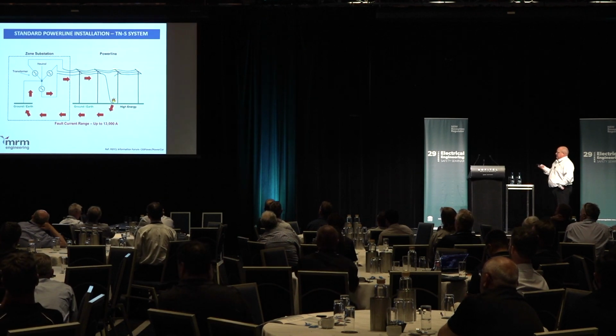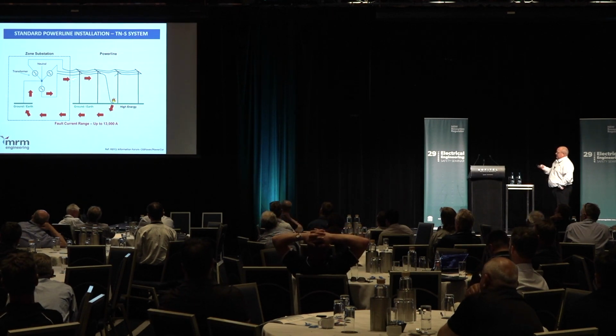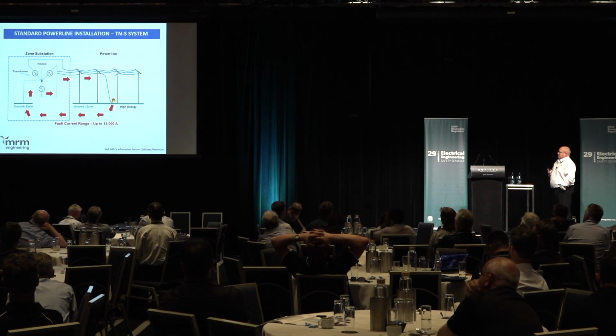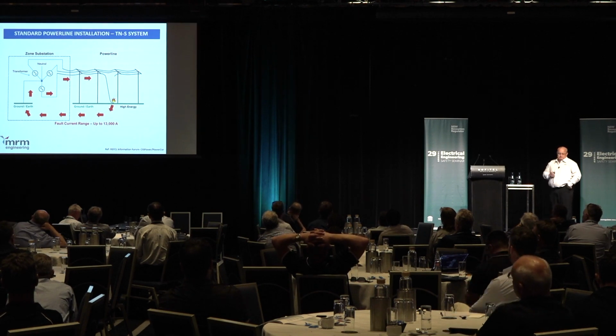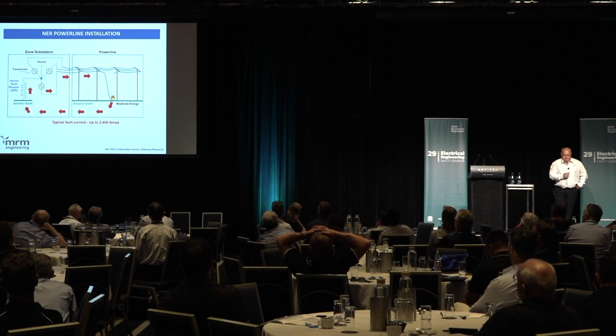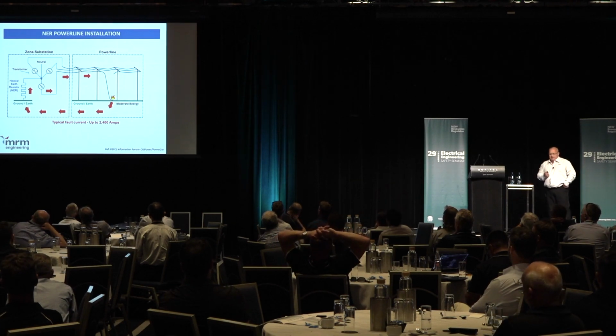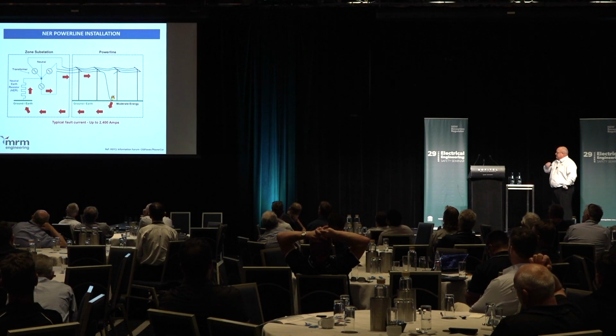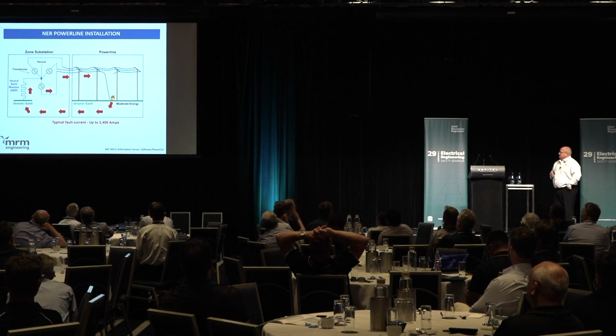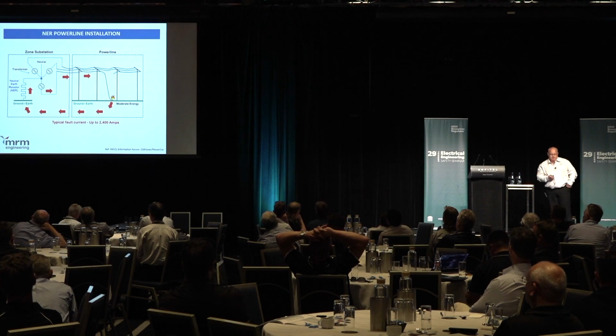The current flows through the capacitance. On this one here, when a ground fault occurs, the cable falls to the ground and creates the current path back through. So that's basically what happened at Kilmore, but on a different line, where the cable fell to the ground, initiated a spark, and then caused the fires. Everybody should be familiar with this one with IT earthing. So again, even with 10 amps limited, or up to 10 amps, the system still has enough energy in the I squared t to create the spark and the fault to create the fire.